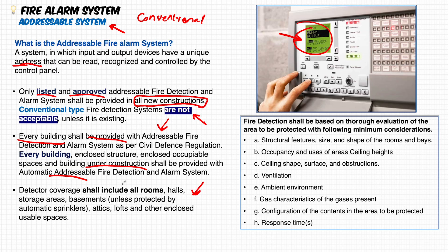Where shall detectors be installed? Previously they were provided only in bedrooms, but per the UAE Civil Defense Code 2018, all rooms and all areas shall be provided with a detector — smoke or heat. If the area is enclosed by walls, ceiling, and a door, it shall have a smoke detector, heat detector, or other suitable type based on design.